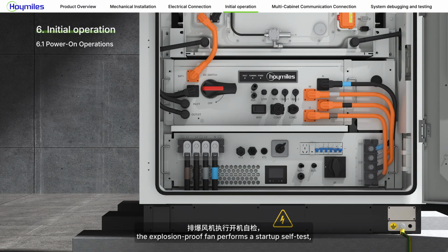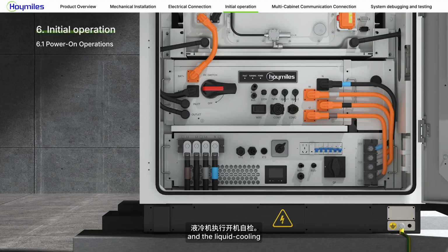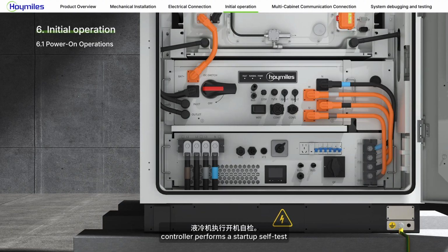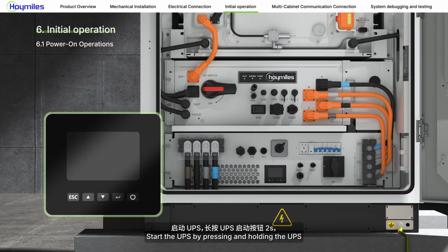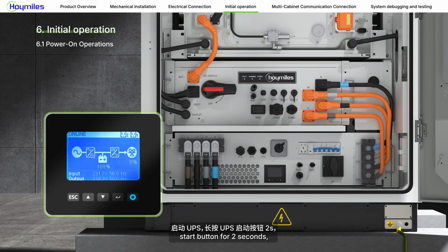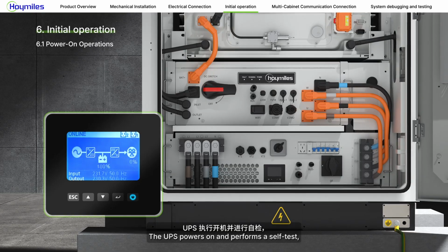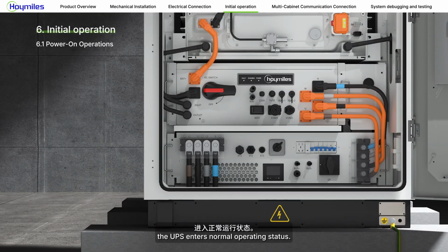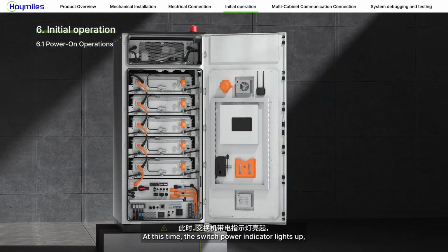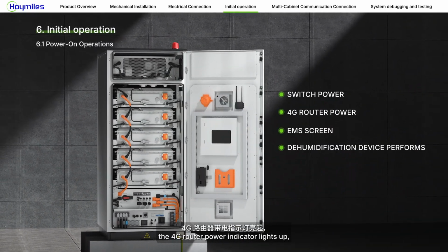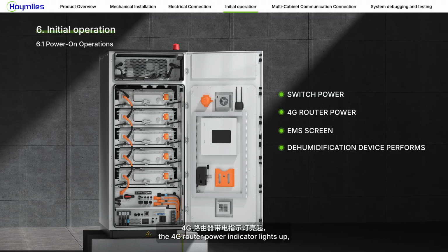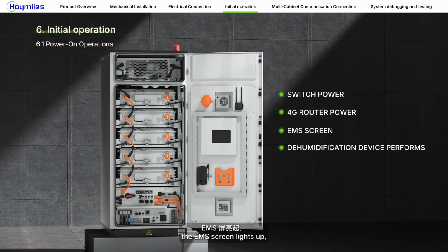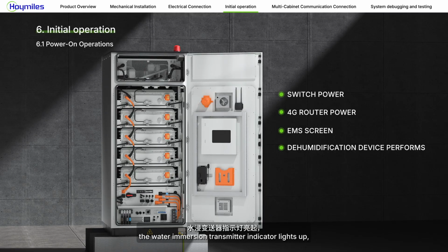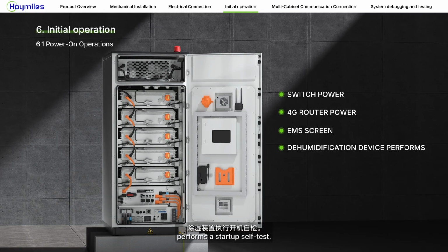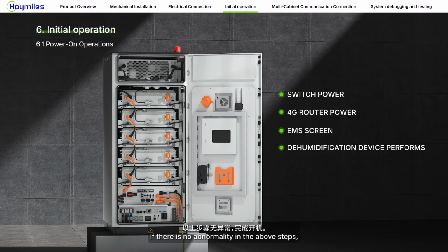At this time, the explosion-proof fan performs a startup self-test, and the liquid cooling controller performs a startup self-test. Start the UPS by pressing and holding the UPS start button for 2 seconds. The UPS powers on and performs a self-test. After the self-test is completed, the UPS enters normal operating status. At this time, the switch power indicator lights up. The 4G router power indicator lights up. The indicator panel lights up. The EMS screen lights up. The water immersion transmitter indicator lights up, and the dehumidification device performs a startup self-test. If there is no abnormality in the above steps, the power on process is completed.